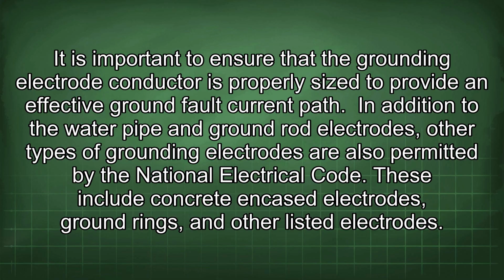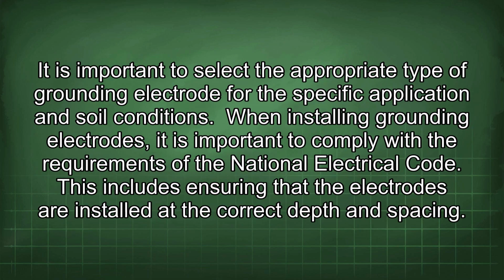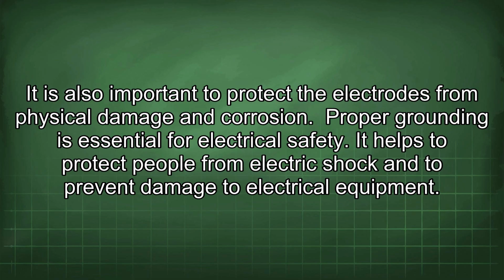In addition to the water pipe and ground rod electrodes, other types of grounding electrodes are also permitted by the National Electrical Code. These include concrete encased electrodes, ground rings, and other listed electrodes. It is important to select the appropriate type of grounding electrode for the specific application and soil conditions. When installing grounding electrodes, it is important to comply with the requirements of the National Electrical Code. This includes ensuring that the electrodes are installed at the correct depth and spacing. It is also important to protect the electrodes from physical damage and corrosion.